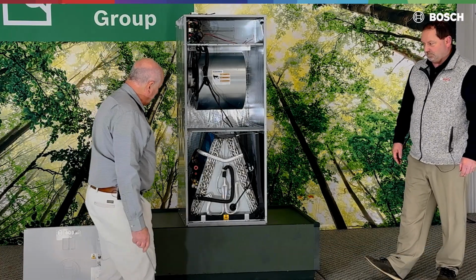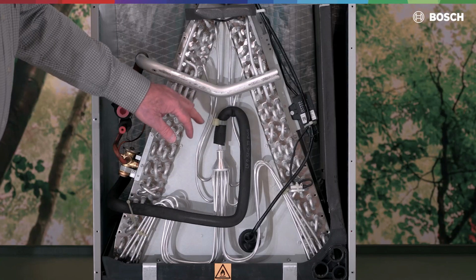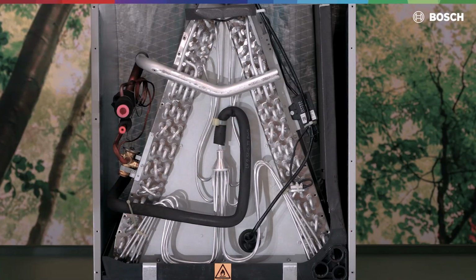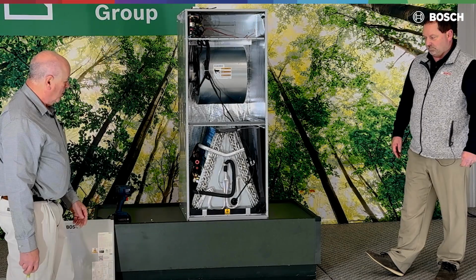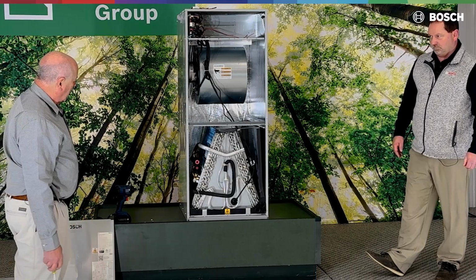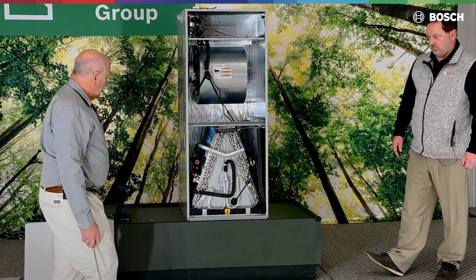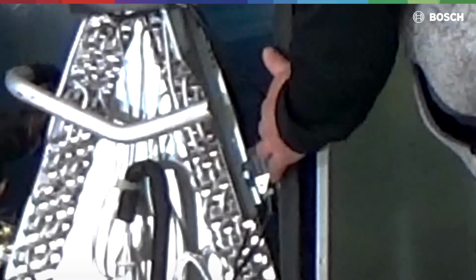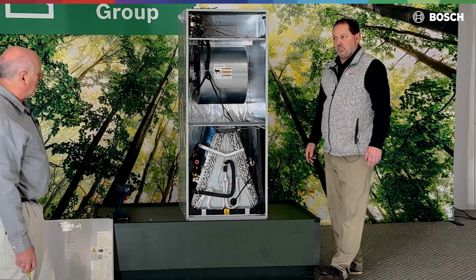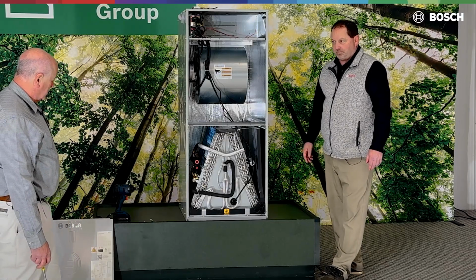A couple other things to note about the Bosch. We have a 4-row coil. A lot of the other coils might be a 2-row, 3-row. A little more volume, a little more capacity, does a great job. Take a look inside the coil. This is a hydrophilic coating. That's a blue coating. Hydro is water, philic is loving. The goal is to get the water off the coil as quick as possible.